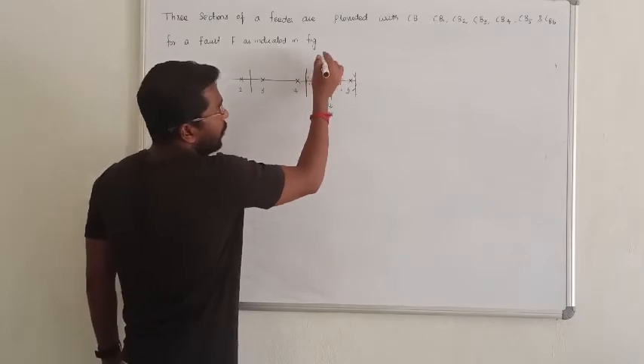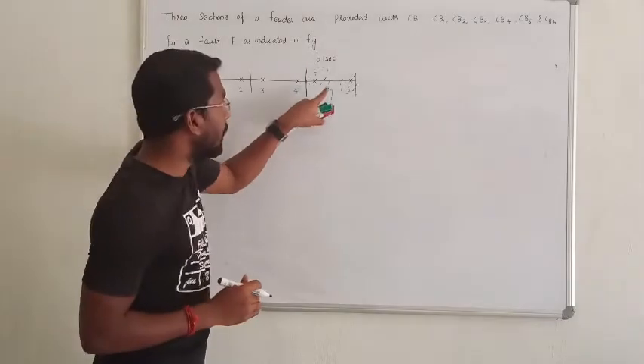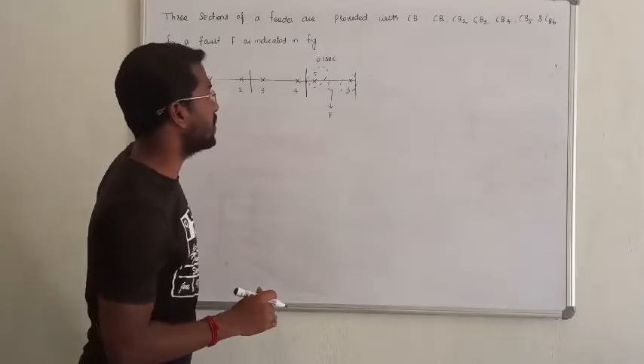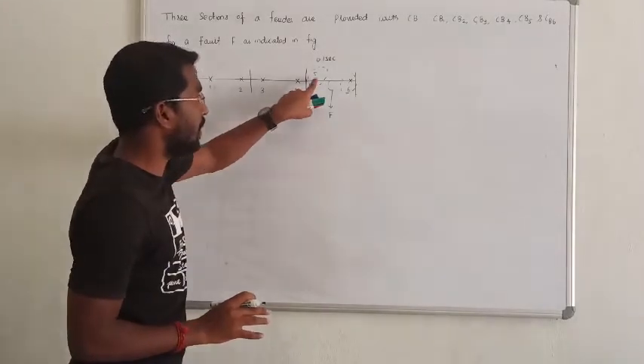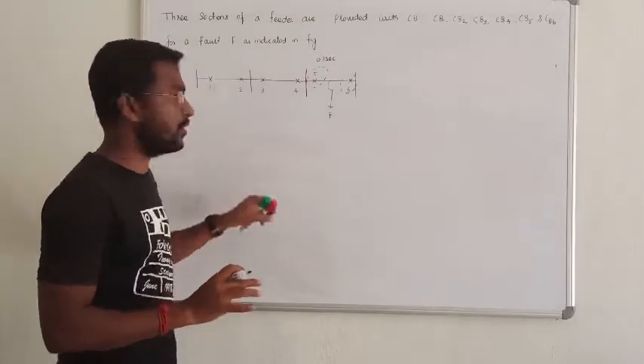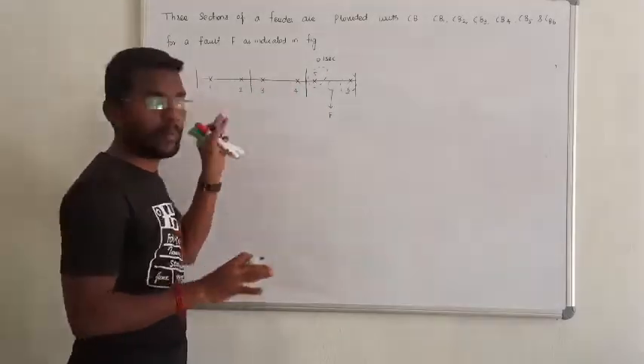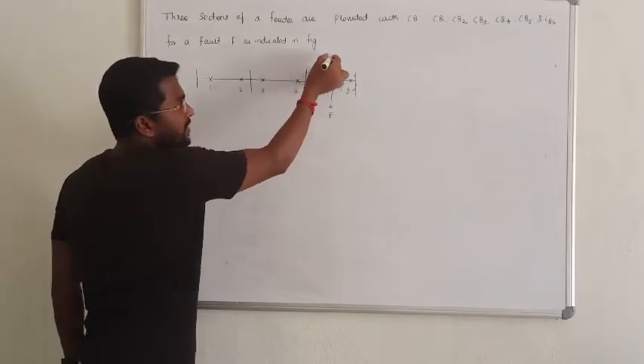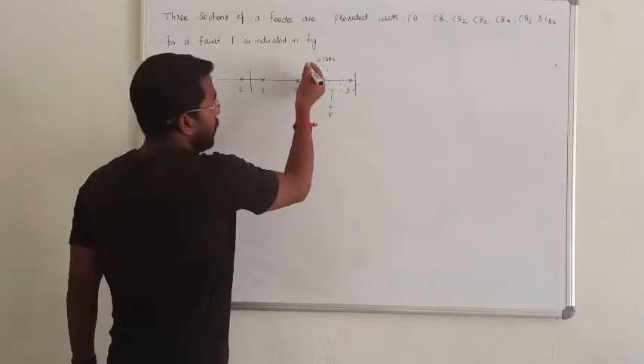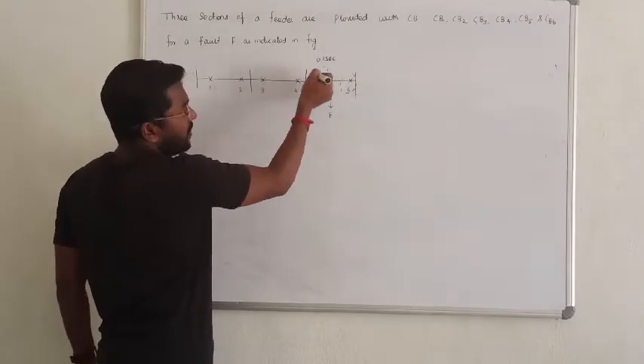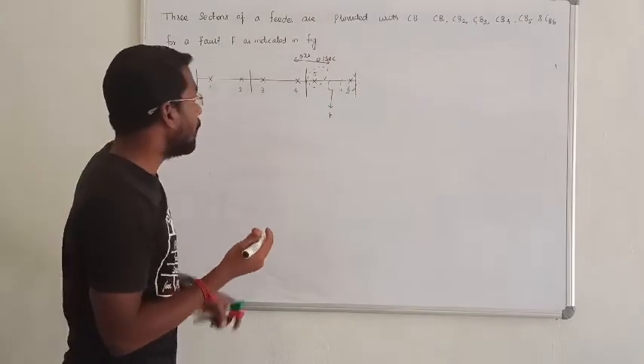The first relay operates at a certain time, say 0.1 seconds. If it fails to operate, the next circuit breaker will operate after a time delay, for example 0.3 seconds. This is how we set the timing sequence for each relay.